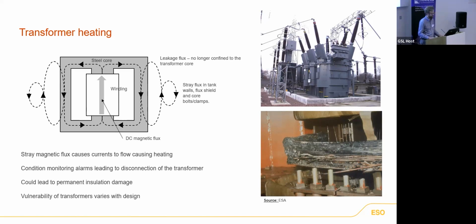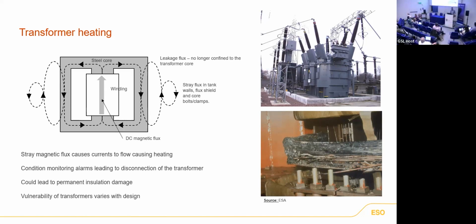That might mean that we see transformers disconnecting because condition monitoring systems detect heating in that transformer. Although, because it's quite localized, it might be just a bolt within the transformer that is heating up. It might take a while for that heat to come through to the sensors and trip it off. So it could lead to permanent damage to insulation within the transformer, and that's what basically happened to that transformer at the bottom there, in that picture, which is from 1989 in North America.